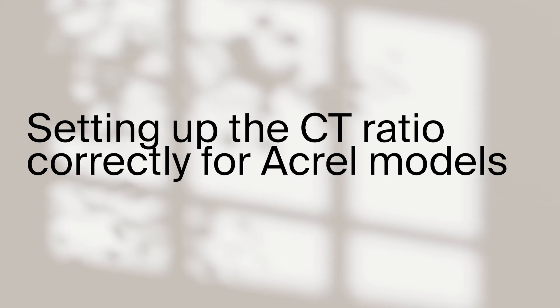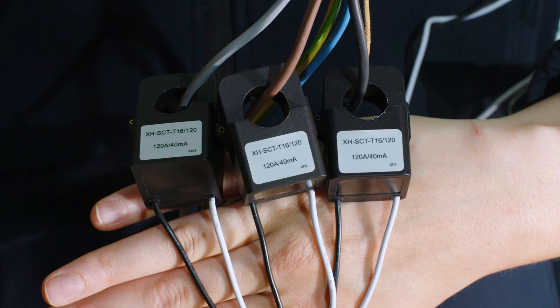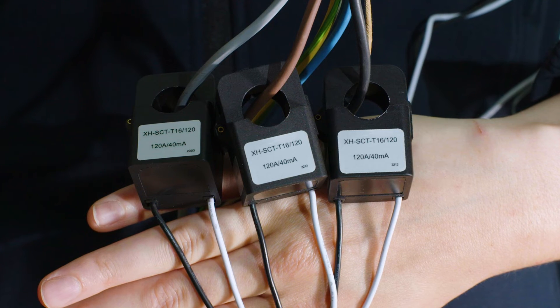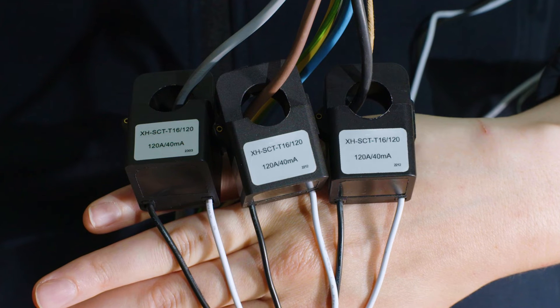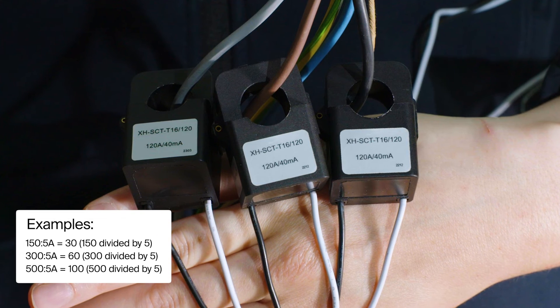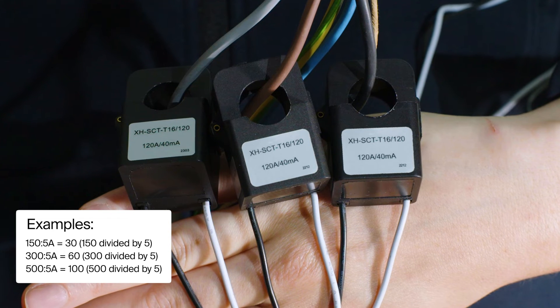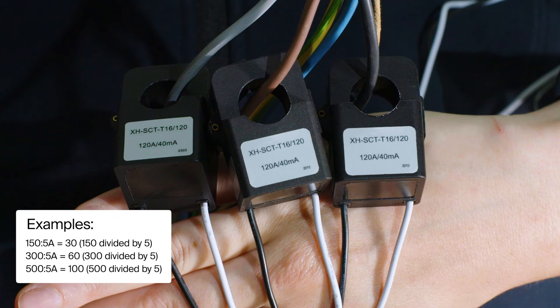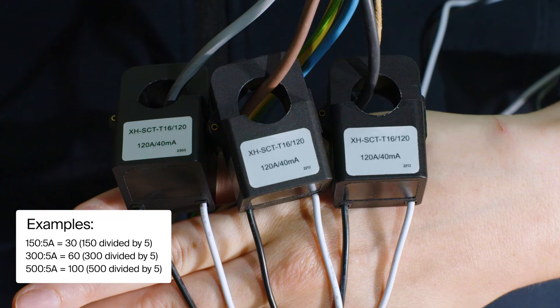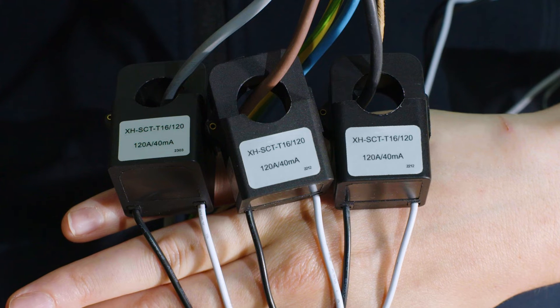Step four: Now let's make sure the CT ratio of the meter is set up correctly. This setting depends on the CT clamps you have chosen. Check the label on the clamps for the CT ratio. For example, if you have clamps with a ratio of 150 to 5 amps, you'll need to set the ratio to 30 (or 150 divided by 5). For clamps with a ratio of 300 to 5 amps, set the ratio to 60 (or 300 divided by 5). Here's how you can do it.